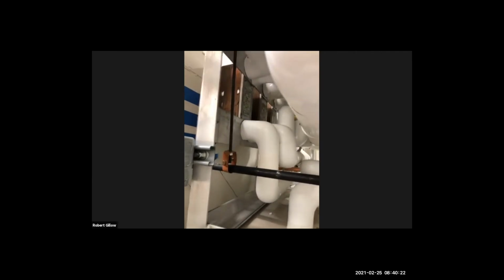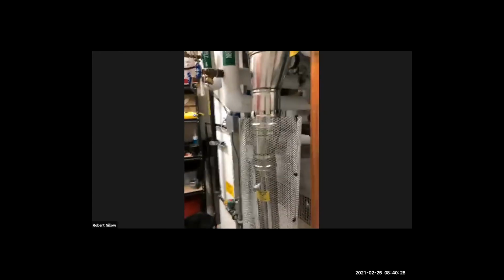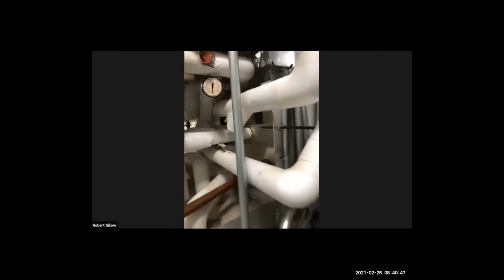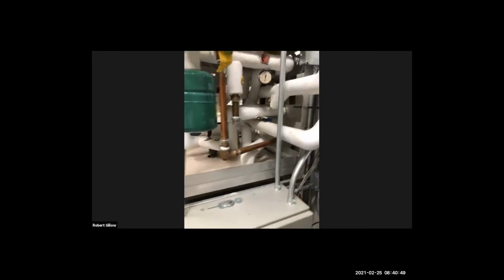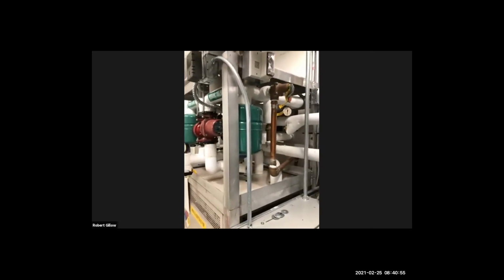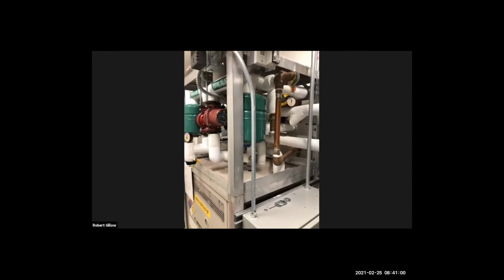What you can see is that there are 3 heat exchangers installed on the back of the unit. The middle one is used for the first heat exchange between the domestic water and the reused water. And each stream will go a further step to do a second heat exchange with the hydronic loop provided by the heat pump. As I just mentioned, the processed water comes in and out from the left side of the heat recovery system.